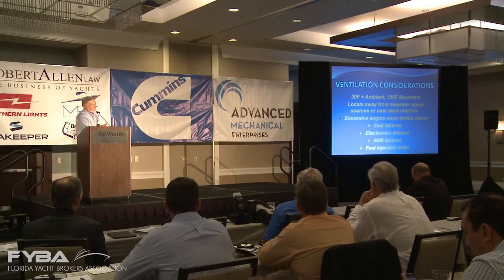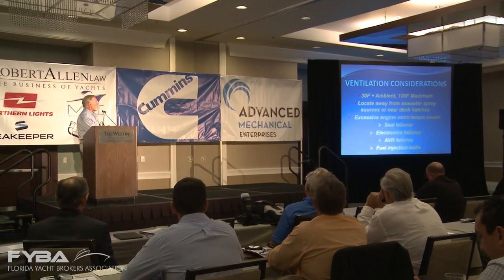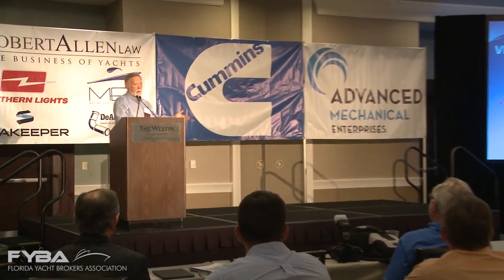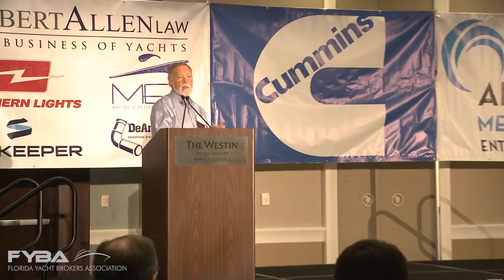The big problem with high temperatures in the engine room is downstream failures — things never intended to be replaced, or never expected to fail, begin to fail. The four categories that are a dead giveaway of excessive heat in the engine room are seal failures, electronics failures, automatic voltage regulator failures, and fuel injection system leaks. Those are a big red flag that says it's too hot, there's a problem, figure out what it is. This is no small thing, and it's an epidemic right now.